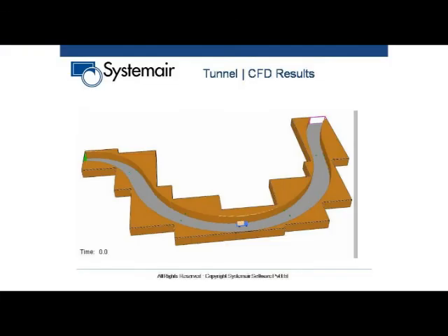The vehicle in front can obviously go out from the smoke, but if the smoke comes back, then the vehicle in the back will be trapped absolutely. So we had to make sure that the smoke got out from here. Here you can see a truck fire.